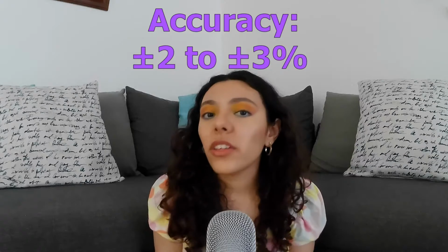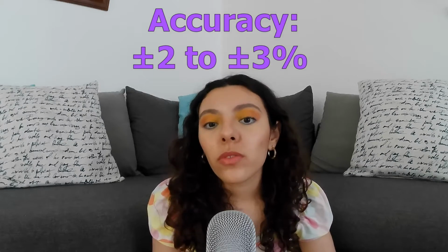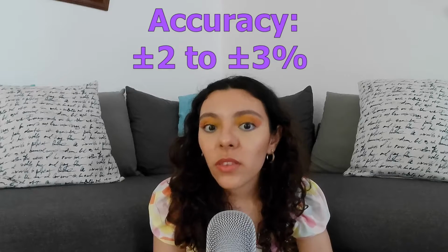The element ages, decreasing its indication by 1 to 2% per year. Accuracy is typically ±2 to ±3% relative humidity, and the element can measure 5 to 95% relative humidity, RH. Its use has been decreasing due to maintenance problems, since the element cannot be used in atmospheres with a lot of dust, with sulfur dioxide, acid fumes, ammonia, alkaline fumes, acetylene, ethylene oxide, and atmospheres contaminated with salt.